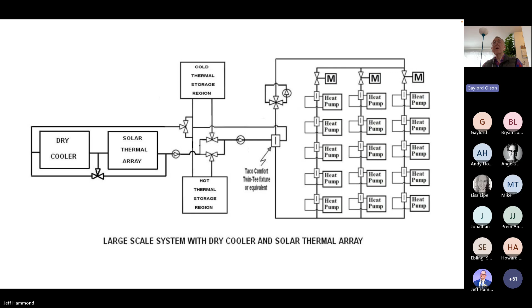you could couple these primary loops together with a simple donut fixture, which could be made as a donut, as shown here at the bottom right, or it could be made with 4 T-junctions and 4 elbows, standard plumbing items. But basically, this is a way to make sure that water will flow through both loops rather than only one, if you have the same flow rate in both primary loops.